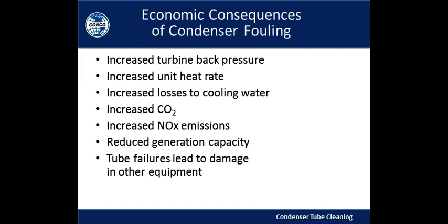You can spend the weekend in the boiler cutting out tube samples to find out that it was foreign matter in the condensate that ultimately caused the damage. But be aware of that. And tie those to your ROI rationalizations. So if you're being challenged on your tube cleaning procedures and processes and decisions, don't forget to provide a satisfactory economic return statement. And include some of these things, because it's all true.